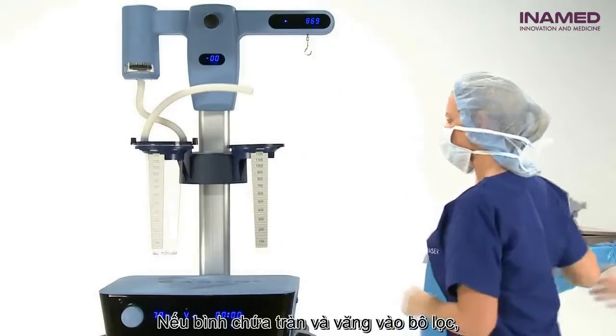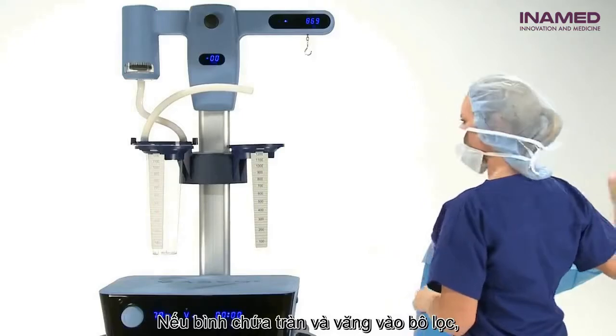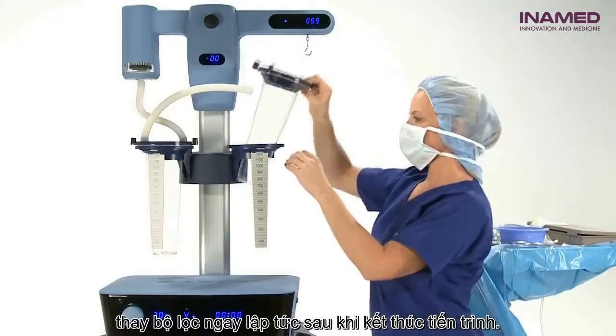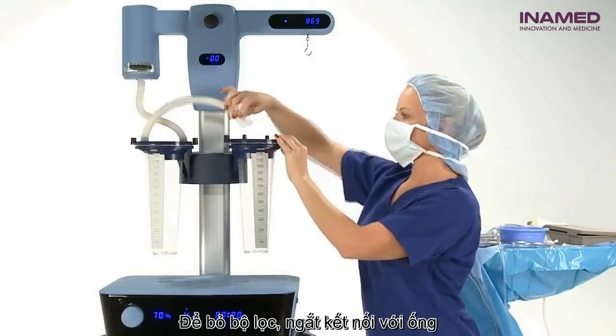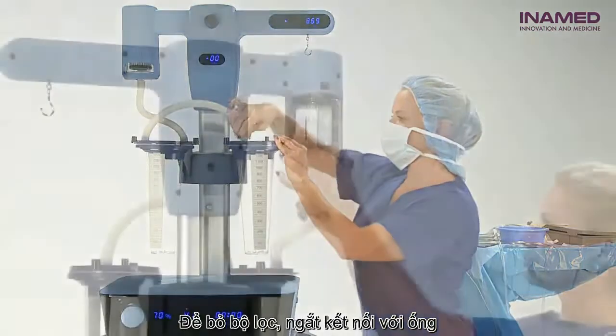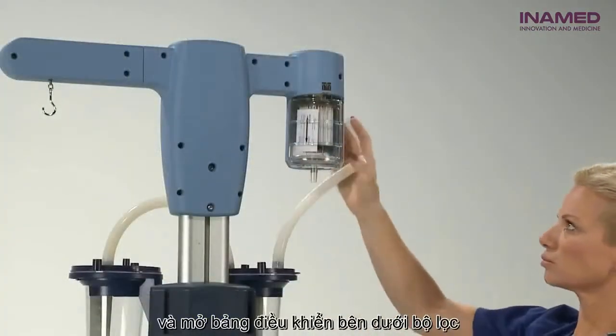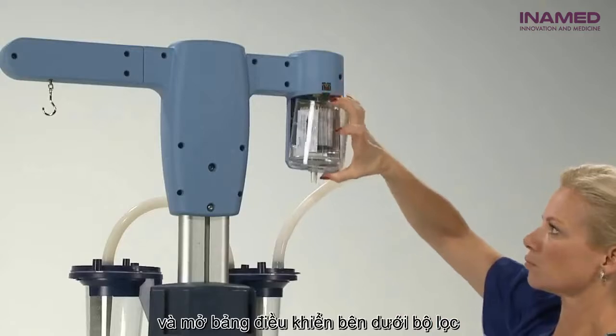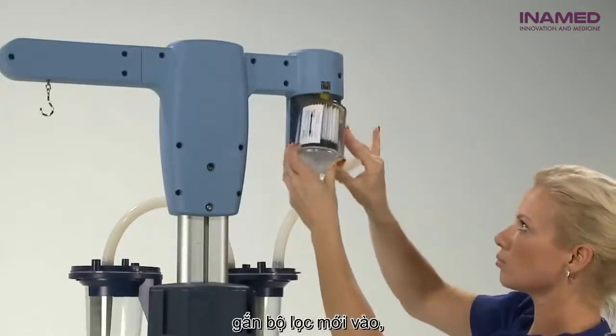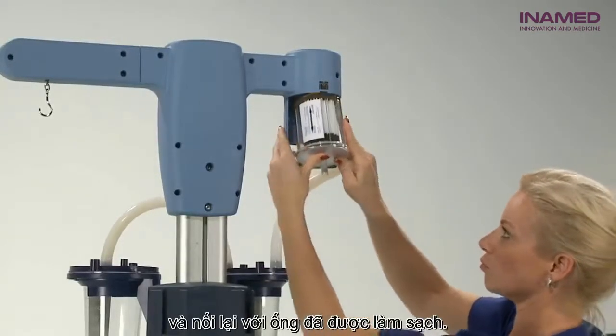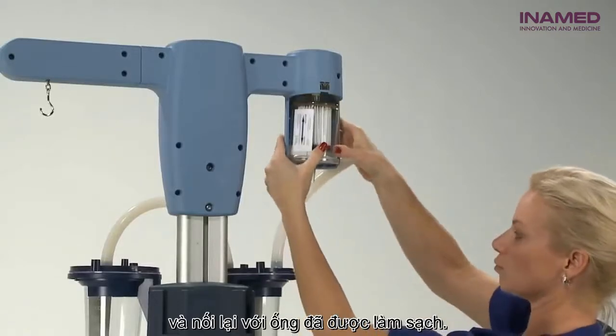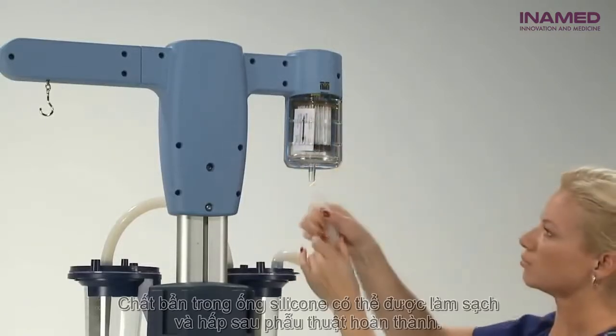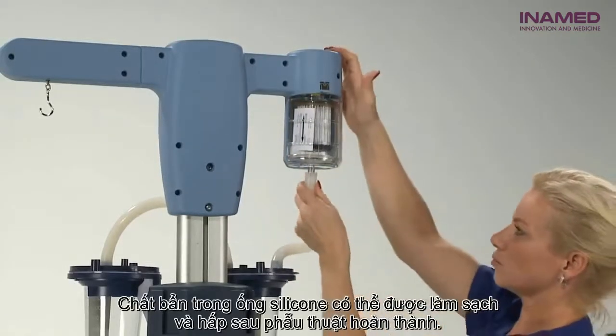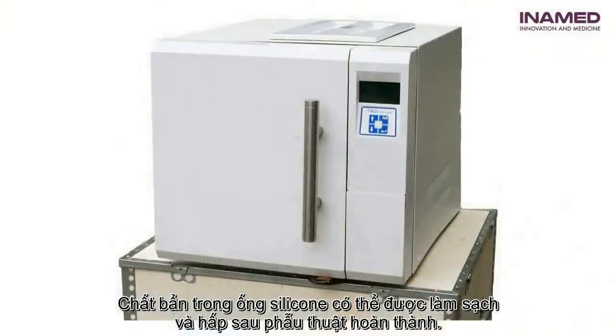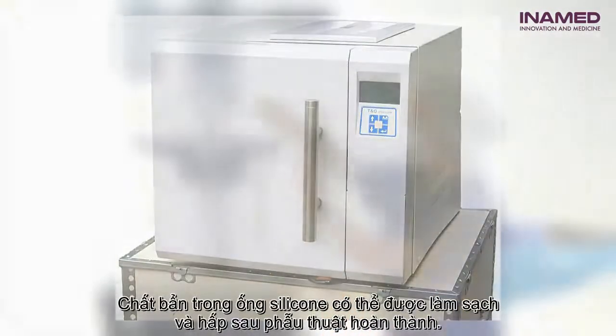If the canister overflows and fluid reaches the filter, replace the filter immediately after the procedure. To remove the filter, disconnect the silicone tubing and open the panel behind the filter chamber. Insert a new filter and reconnect to clean silicone tubing. The contaminated silicone tubing can be cleaned and autoclaved after the procedure has been completed.